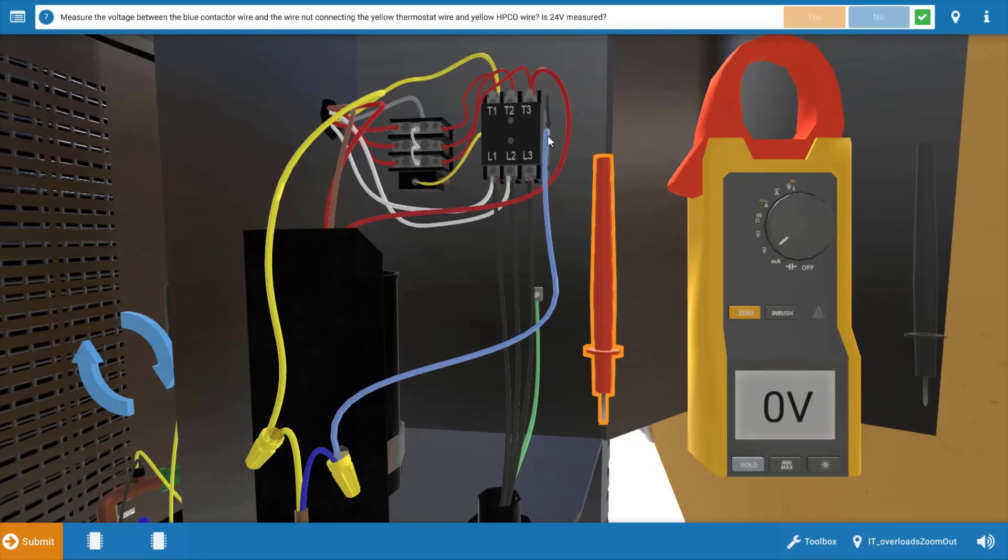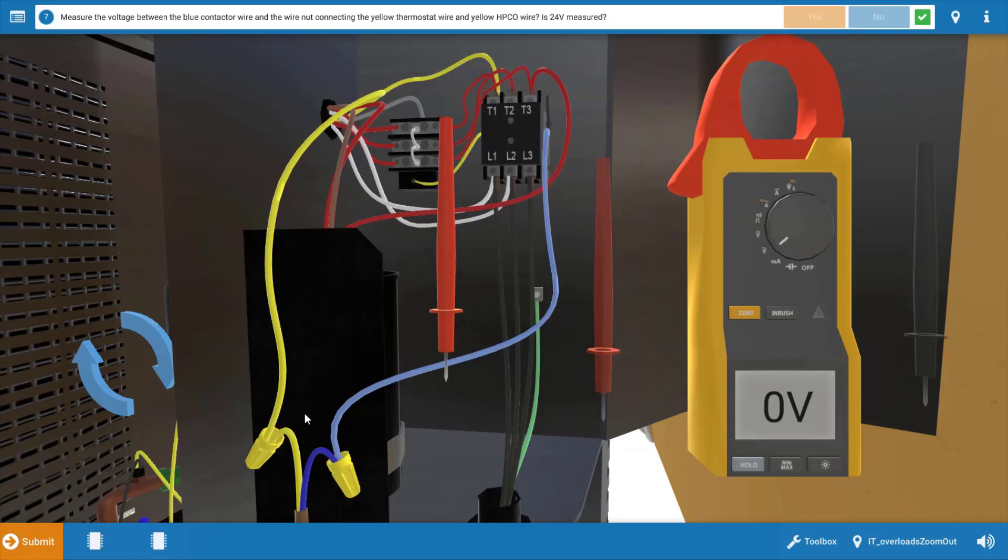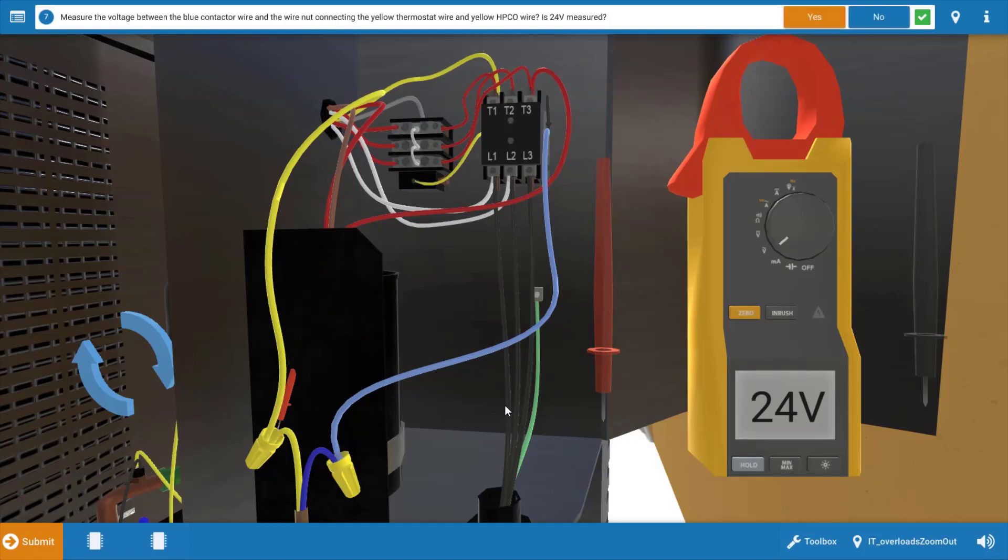We're going to click no on the procedure guide that we've measured zero volts, and we're going to leave our black lead right on the blue connection and do what they call hopscotch troubleshooting. Our next step is to take the red lead and place it at this yellow wire nut here on the glowing orange hot spot. This is going to verify power out of the thermostat, and we do in fact have 24 volts here.